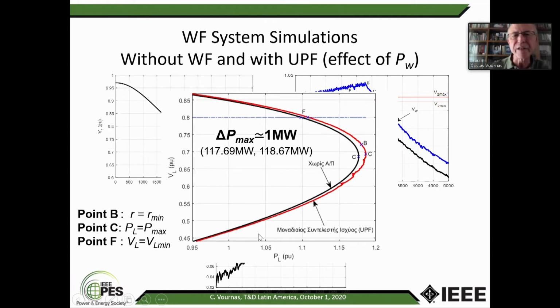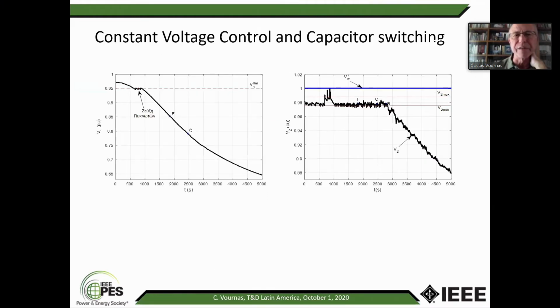Now, what is this curve here? It is the load consumed power, PL, versus the load voltage. So you see point C here is the maximum power, and you see it's at a low voltage. If you do not care to go that far and you say, okay, for low voltage, I want to stop here, then you have your other limit, which is marked by the F, which is the low voltage limit. This is the voltage stability limit. This is the static limit due to low voltage. Okay, so you see with just having the wind blowing, you gain a little bit, but just a little bit.